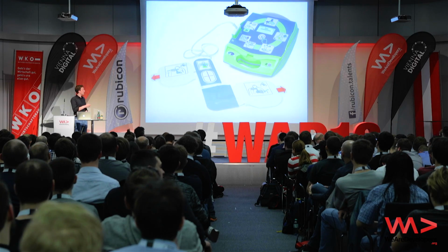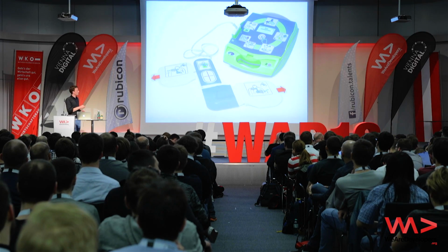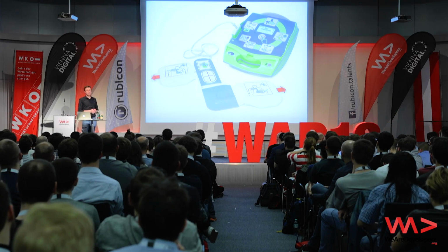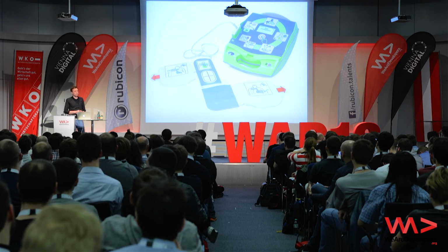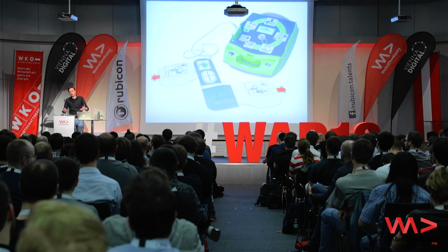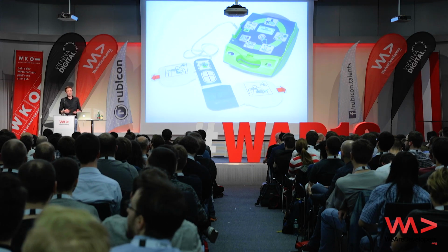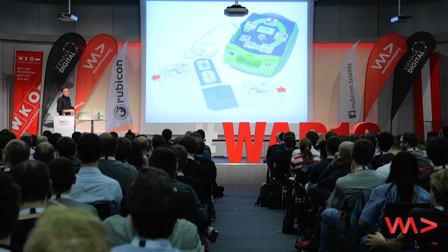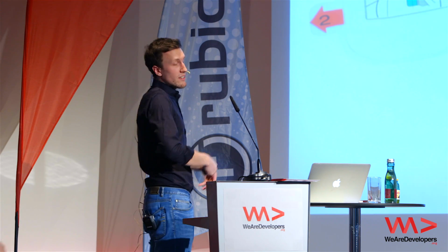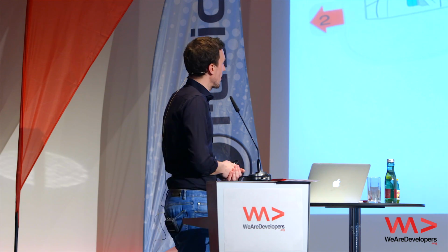And as soon as it tells you that, then in the new systems, there's only one button, it starts to flash, and it's a red button, and it's a big button, and it tells you shock now, and don't touch the patient. That's the only interaction you can actually do. Or it tells you don't shock, continue with classic CPR, 30 to 2. But that's the only possible interaction. And then it counts for itself up until 2 minutes, because the phases between analysis should be 2 minutes. And then does the overall thing again. So it always tells you what to do, when to do it, and there is no escape route. There is no going the wrong path, doing something wrong.